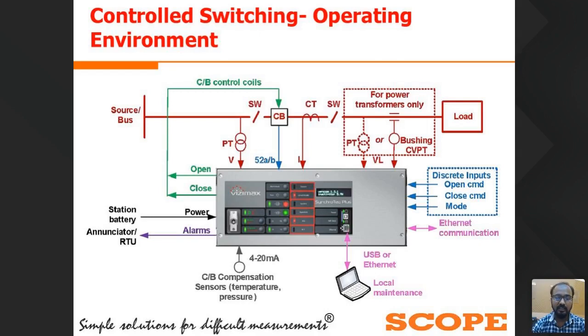After that, we are taking the other important parameters that we require, that is the reference of system voltage and system current. These two inputs we are taking from the CTs and the PTs. The CSD is continuously sampling the voltage and current. So the CSD has the reference of system voltage and current, and it knows when the system voltage is going to be at peak and when it is going to be at zero. By doing the continuous sampling, the CSD takes the reference of the system voltage peak, system voltage zero, current zero value, and current peak value. So the CSD has the reference of current and voltage, as well as the reference of the breaker operating time.